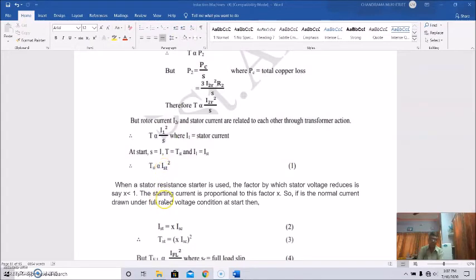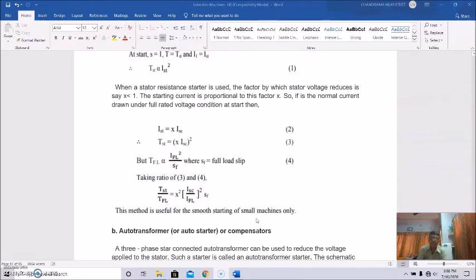Now when a stator resistance is used, the factor by which the stator voltage reduces, if we say it is X, which is less than 1, then the starting current is proportional to this factor X. So if ISC is the normal current drawn under full rated voltage at start, then the starting current should be equal to X times ISC, and the starting torque will be X square ISC square, or X ISC whole square.